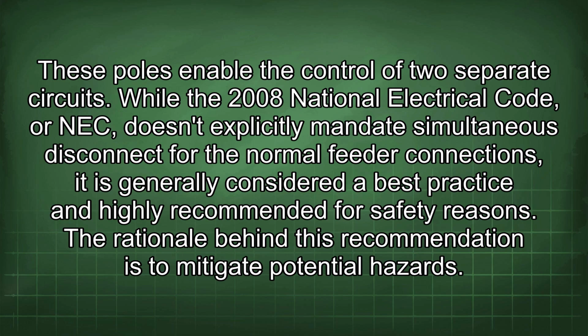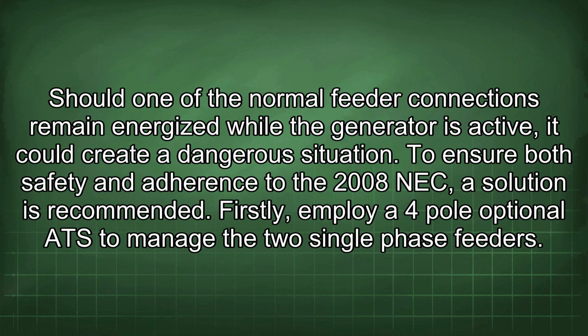While the 2008 National Electrical Code, or NEC, doesn't explicitly mandate simultaneous disconnect for the normal feeder connections, it is generally considered a best practice and highly recommended for safety reasons. The rationale behind this recommendation is to mitigate potential hazards. Should one of the normal feeder connections remain energized while the generator is active, it could create a dangerous situation.